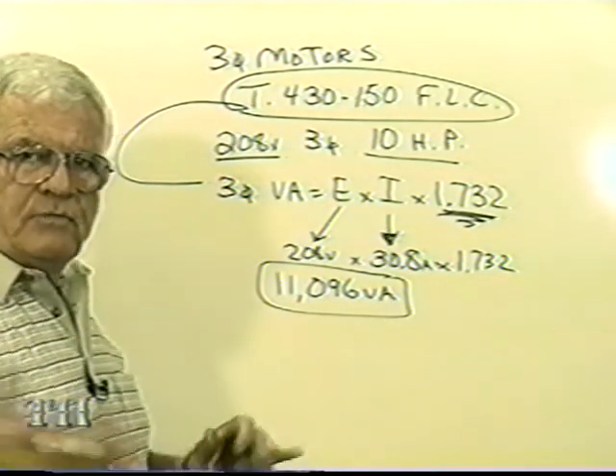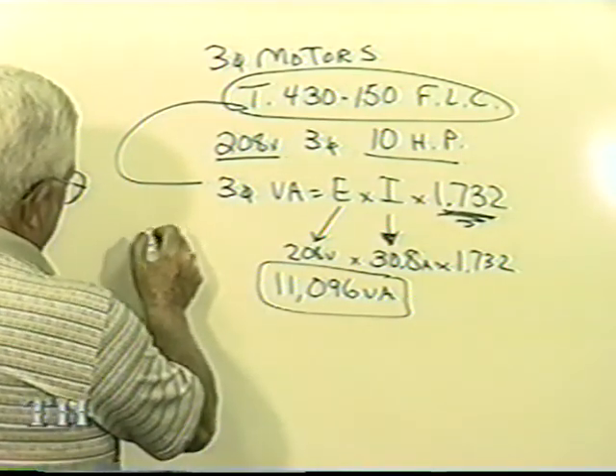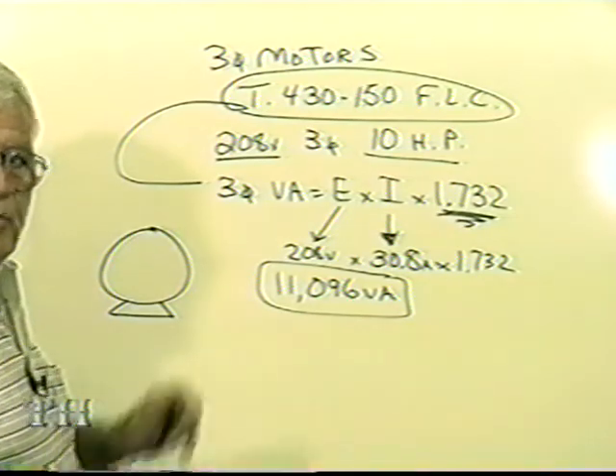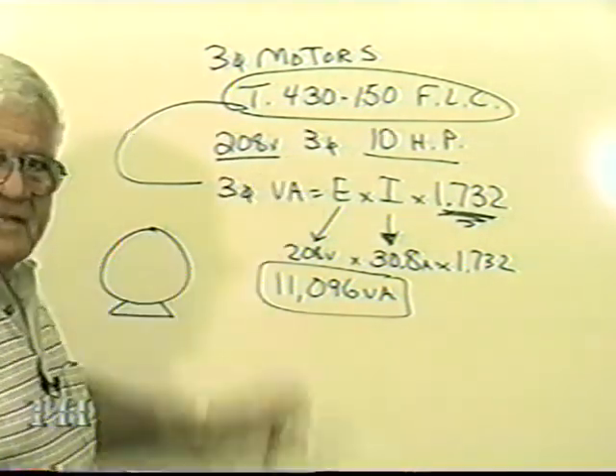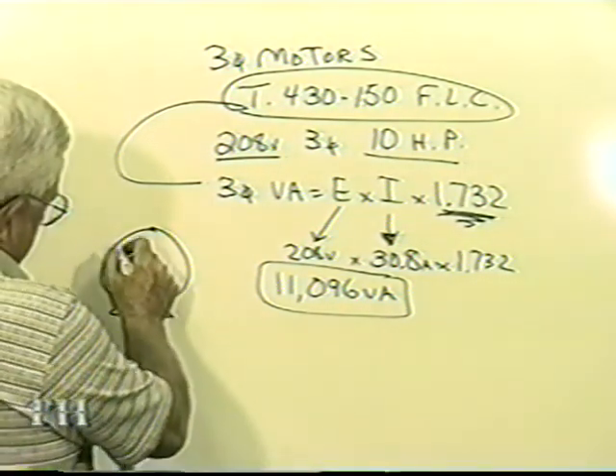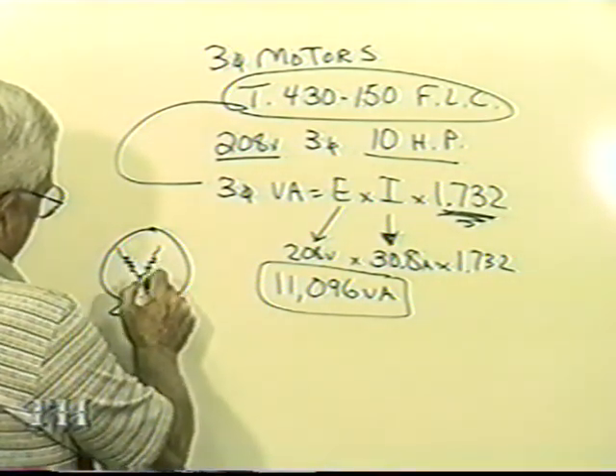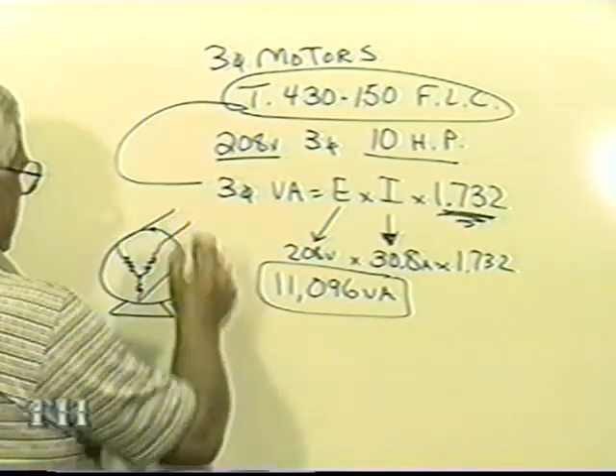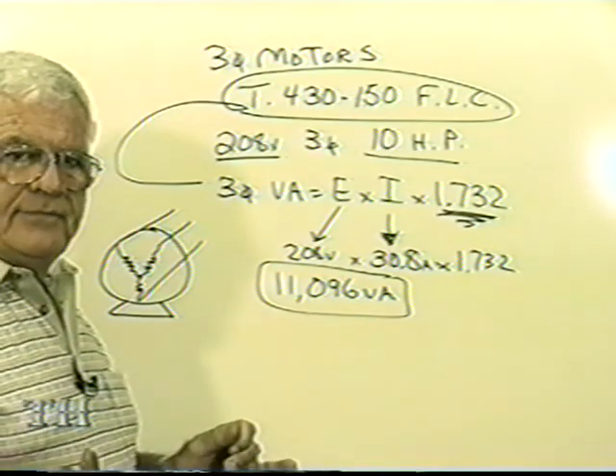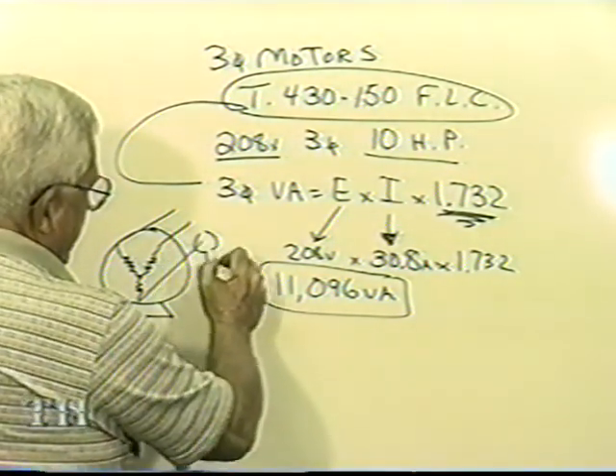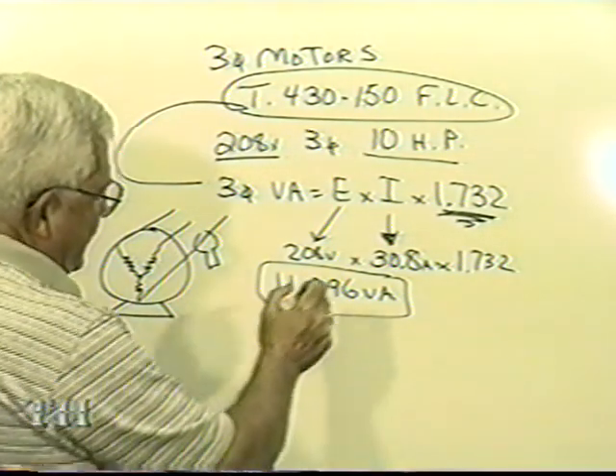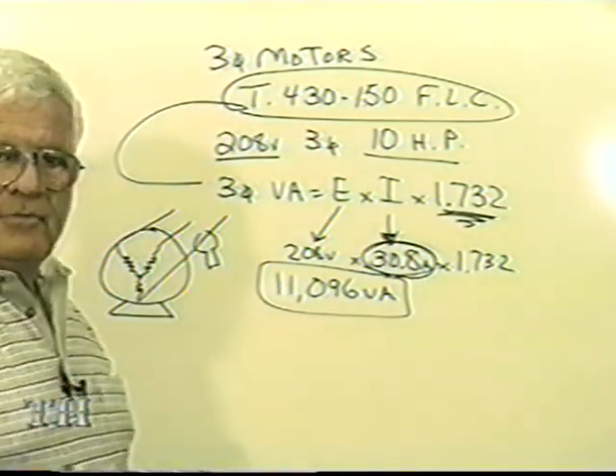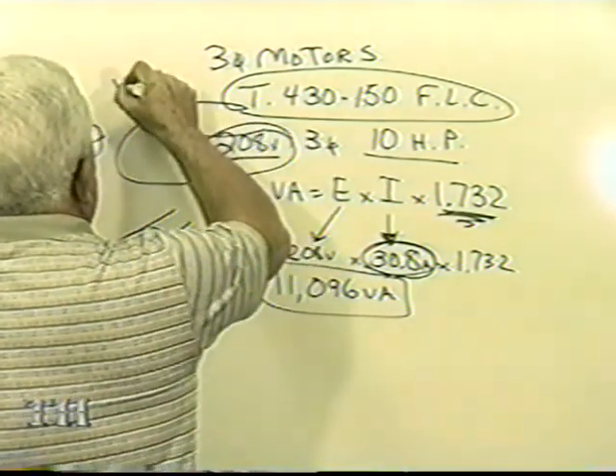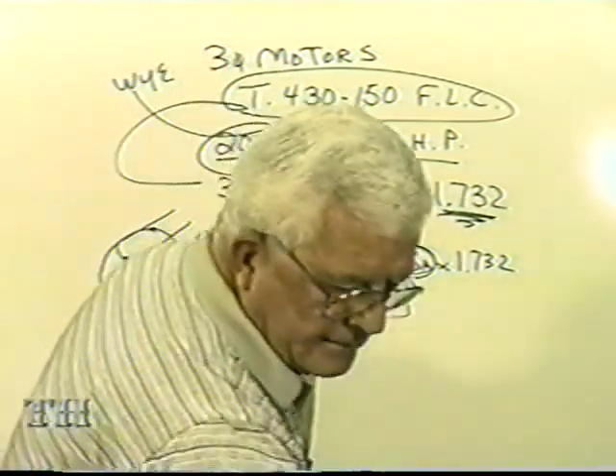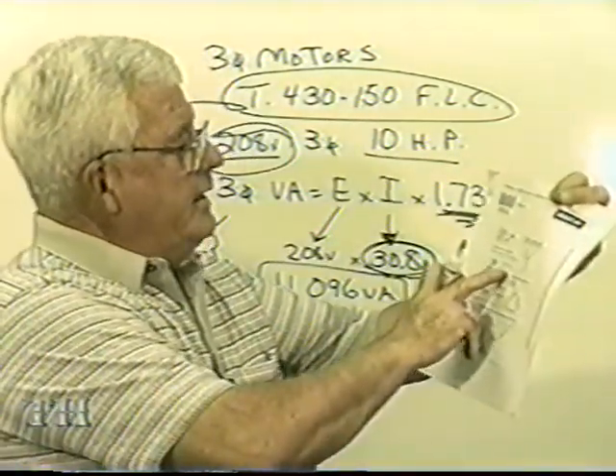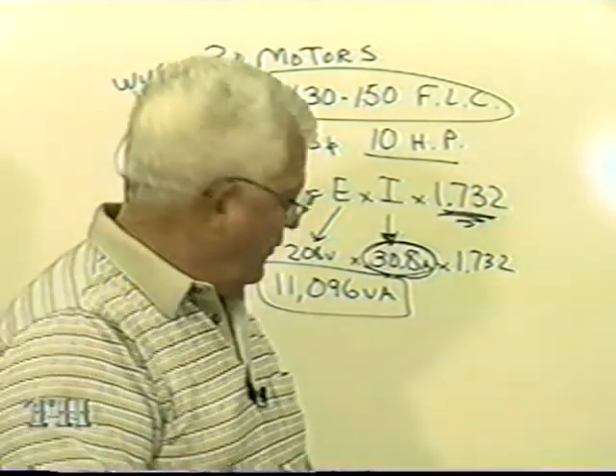But see, watch. If you wanted to turn that into what we've been talking about on this video, let's say this motor, if we could see inside of it. You see this voltage? That's a Y. 208, that's a Y. So if I could look inside this motor, I would see these windings, and they'd look like a Y. And those 3 wires would come out, and I'd make my connections to make that motor run. Now watch. If I put my amp clamp on that line wire, it's going to read fully loaded 30.8. But since this is a Y, you remember we said in our format, like on sheet 1, for a Y that phase amps equal line amps.